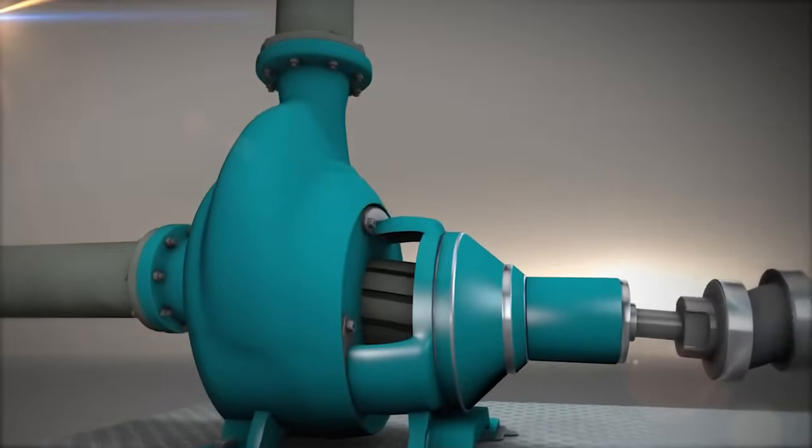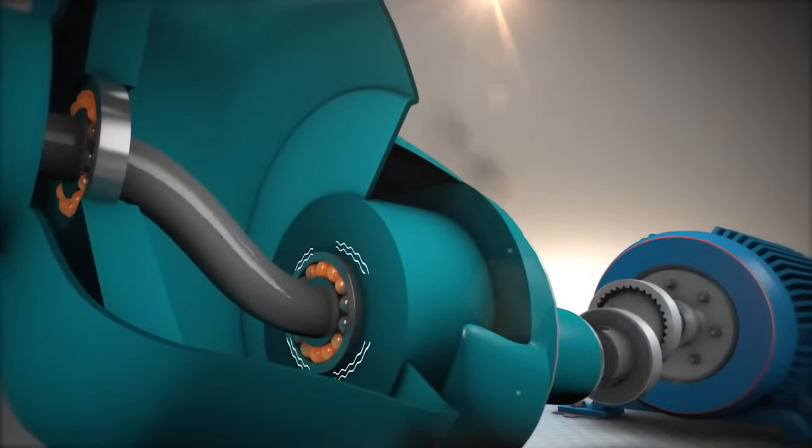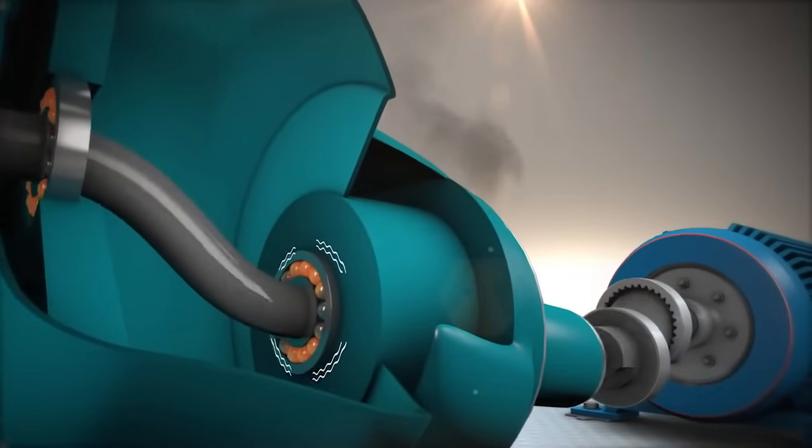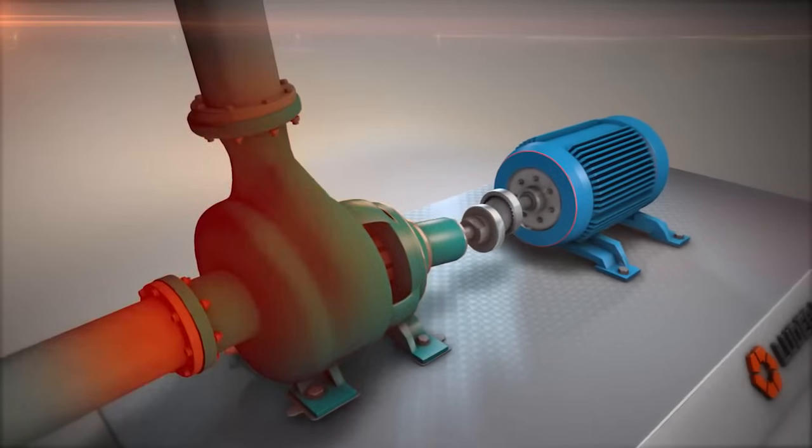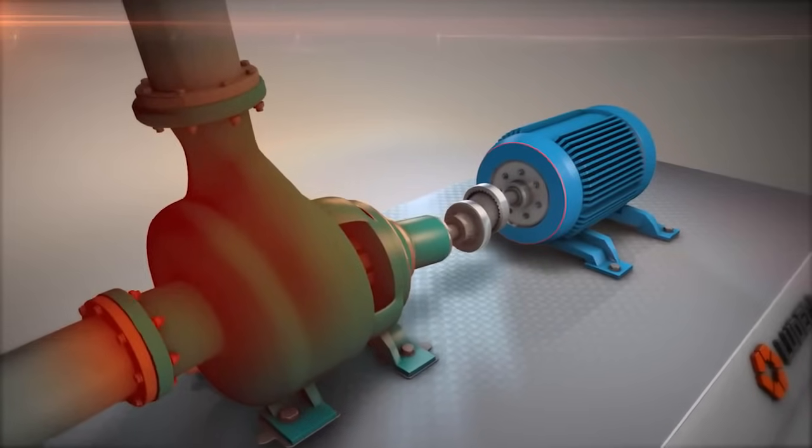The resulting deflection of the pump casing results in internal misalignment of the bearings, inducing vibration and premature failures. Sometimes it is thermal growth that causes pipe stress and the resulting strain, changing the alignment at the coupling.